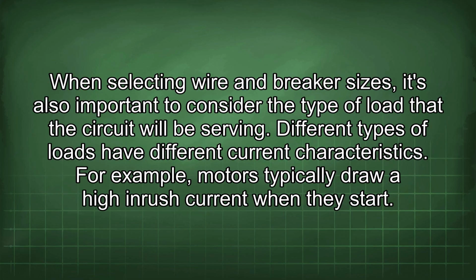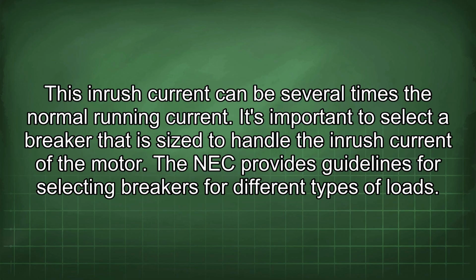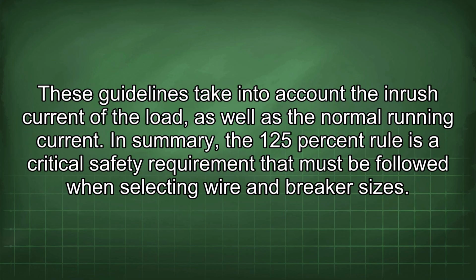When selecting wire and breaker sizes, it's also important to consider the type of load that the circuit will be serving. Different types of loads have different current characteristics. For example, motors typically draw a high inrush current when they start. This inrush current can be several times the normal running current. It's important to select a breaker that is sized to handle the inrush current of the motor. The NEC provides guidelines for selecting breakers for different types of loads. These guidelines take into account the inrush current of the load, as well as the normal running current.